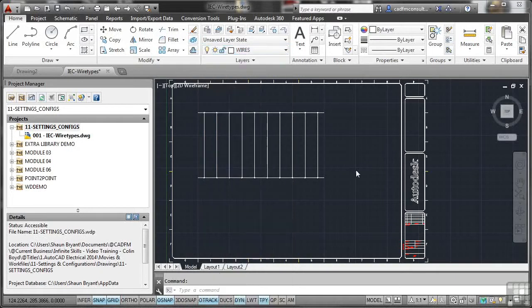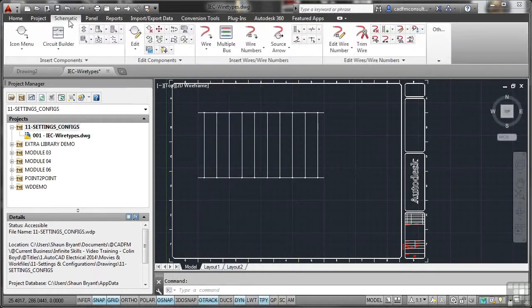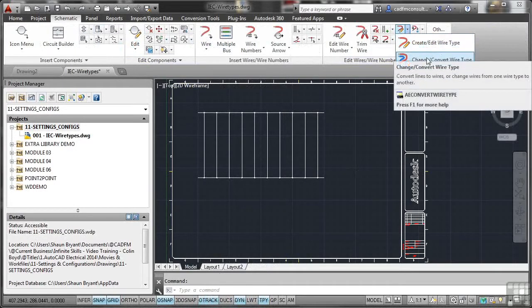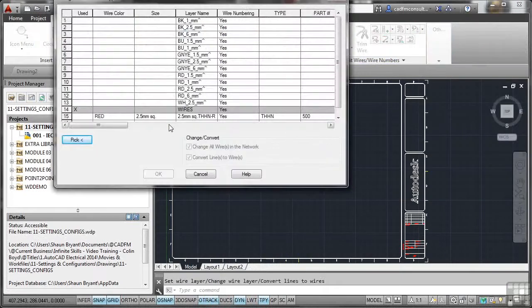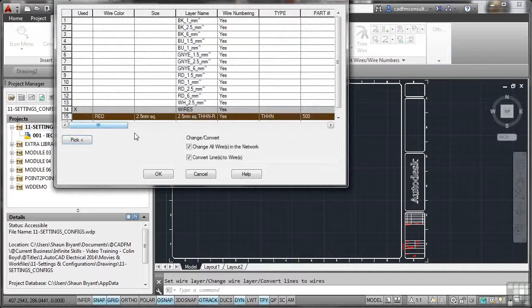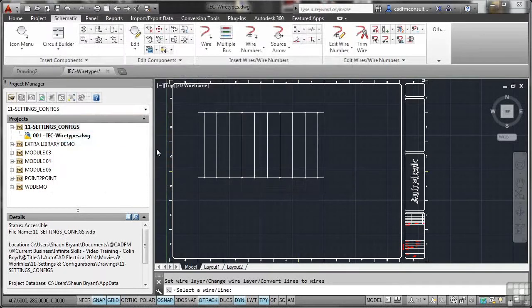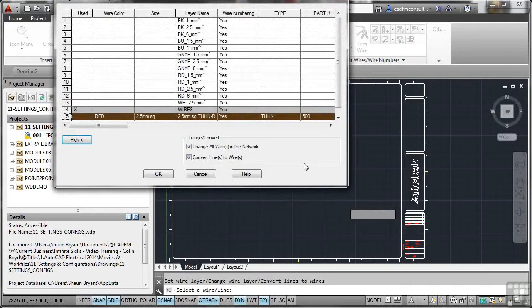We don't need to make that our current layer. Go to the schematic tab, back to the pulldown, and select change/convert wire type. We're going to change and convert our wire type. We can select the wire type we want to use — the one we've just created. Notice the current one with the X in it is 'wires,' because the wiring ladder is on that layer at the moment. I have a choice: change all the wires in the network, or convert lines to wires. I'm going to pick what's in my drawing by selecting 'wire or line,' but note that if you don't click on anything it goes back.